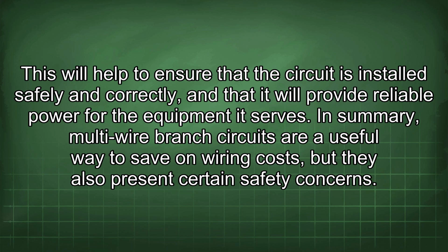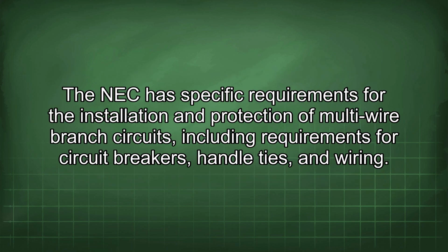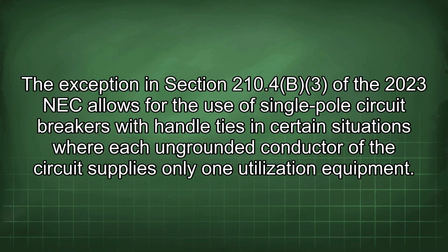In summary, multi-wire branch circuits are a useful way to save on wiring costs, but they also present certain safety concerns. The NEC has specific requirements for the installation and protection of multi-wire branch circuits, including requirements for circuit breakers, handle ties, and wiring. The exception in section 210.4(B)(3) of the 2023 NEC allows for the use of single-pole circuit breakers with handle ties in certain situations where each ungrounded conductor of the circuit supplies only one utilization equipment.